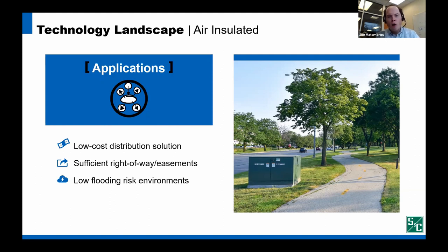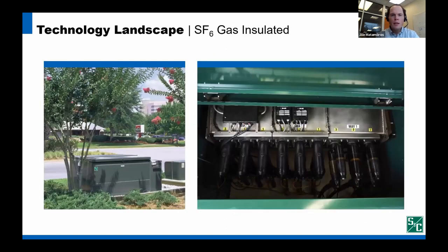With respect to the evolving underground grid, the need for submersible gear drove the development of sealed underground distribution switchgear. The first type of sealed gear we will discuss is SF6 gas insulated gear. SF6 gas insulated switchgear uses SF6 as the dielectric insulating gas instead of air. Here are a few examples of SF6 gas insulated gear, the Vista gas insulated switchgear.